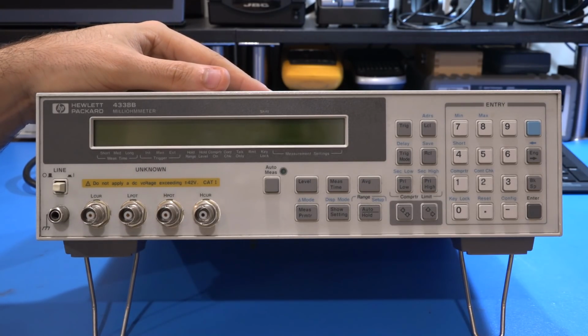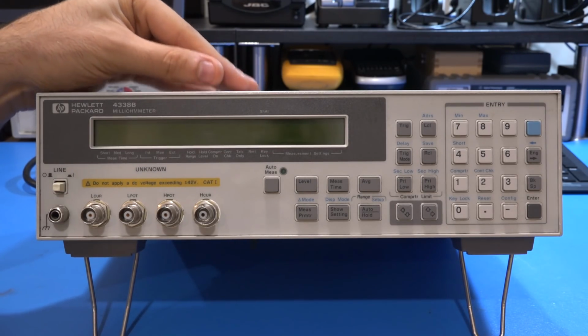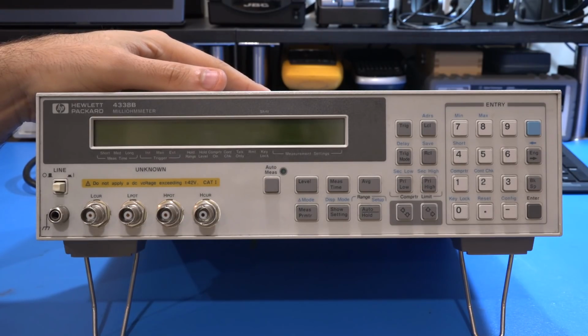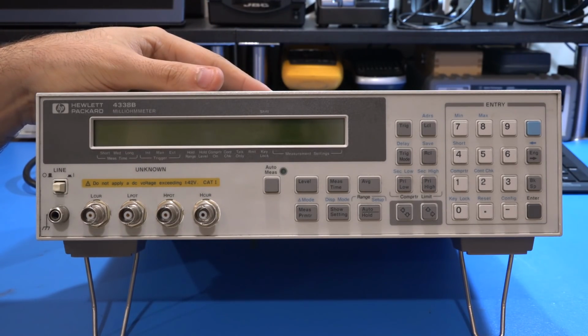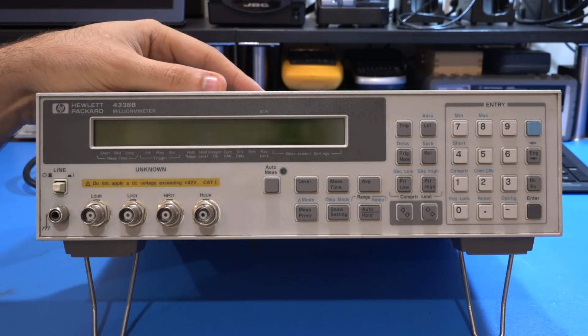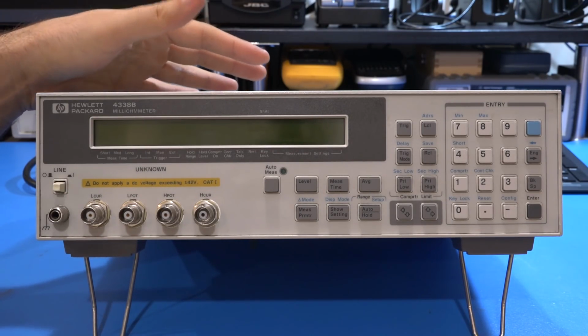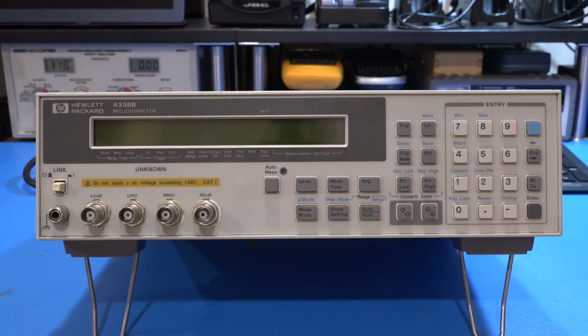This means that you can measure these tiny resistances with very little current. You can always measure a tiny resistance by putting a lot of current through it if you don't have enough dynamic range from your measurement unit. But this, of course, allows you to do it with very little current and measure it at 1 kilohertz. So I'll go over the principle of operation of this. It's similar to an LCR meter in a way, looking at the angles and taking a real part of the current voltage relationship. So it should be pretty cool to see what's inside it and if we can fix that.